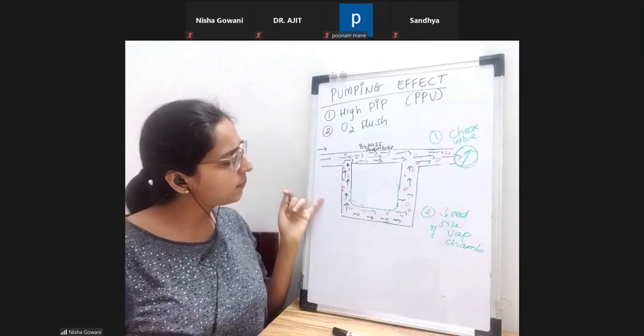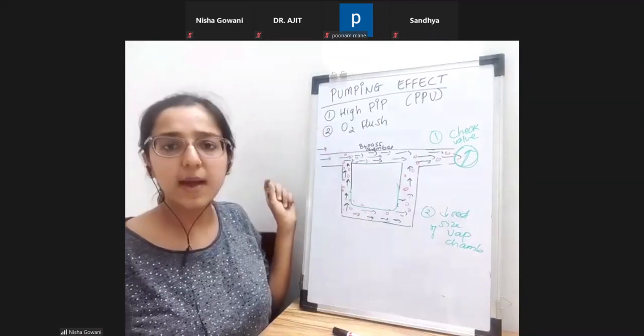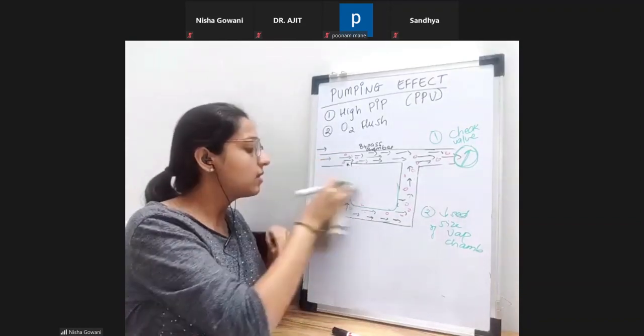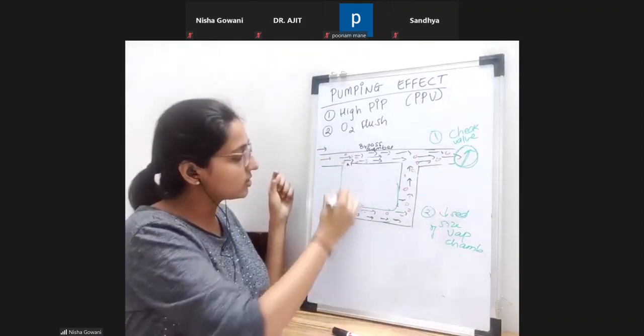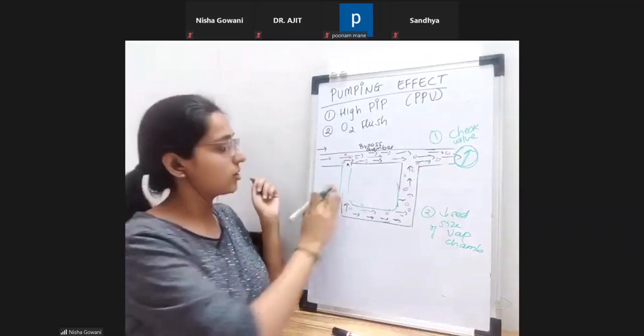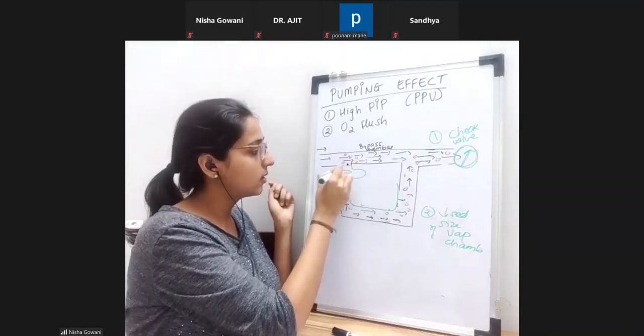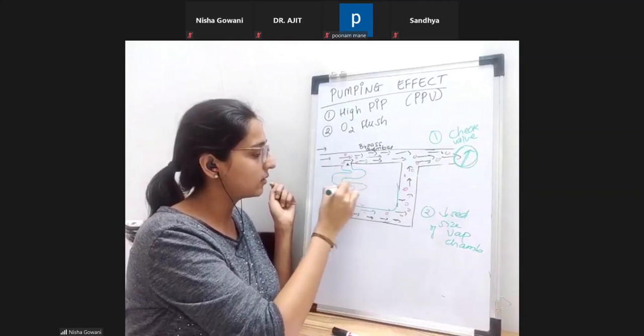Can we prevent the gas from entering the bypass chamber? Let's think, how can we do it? So what they said: this tube which was straight, we will change it. This incoming tube, we'll make it curved.